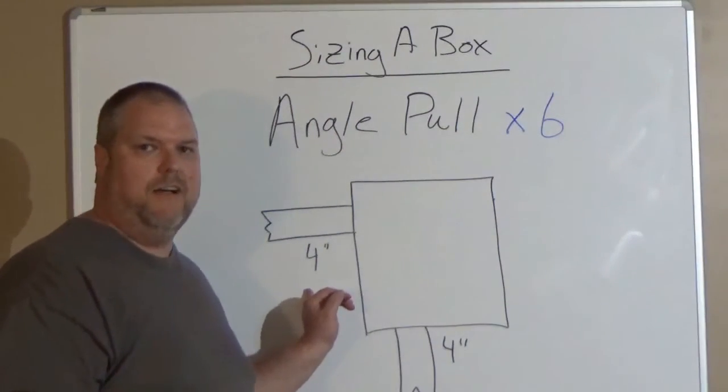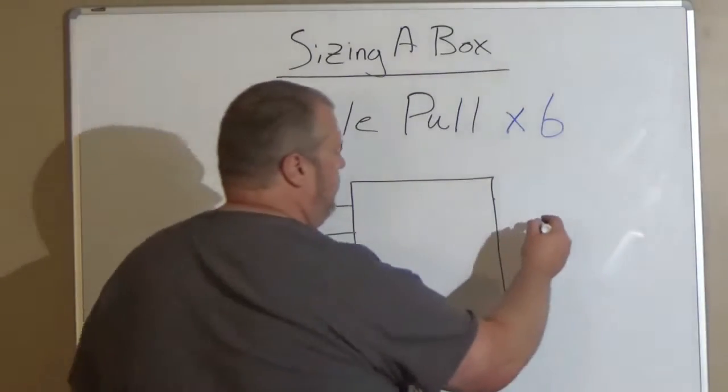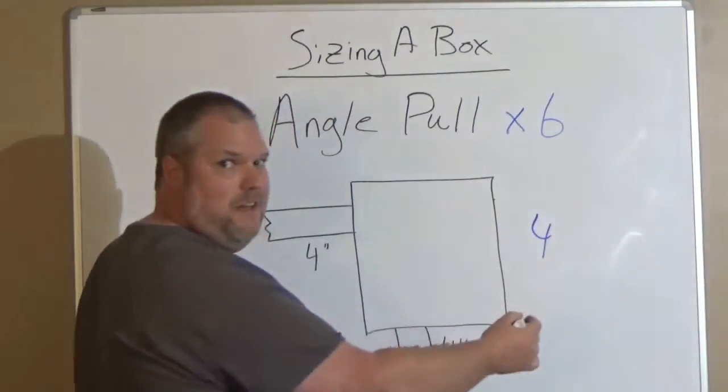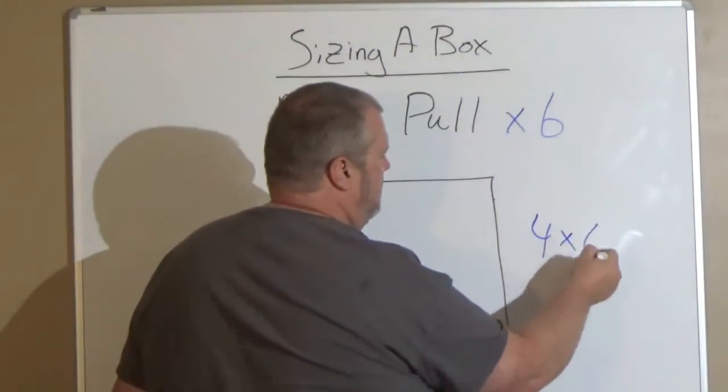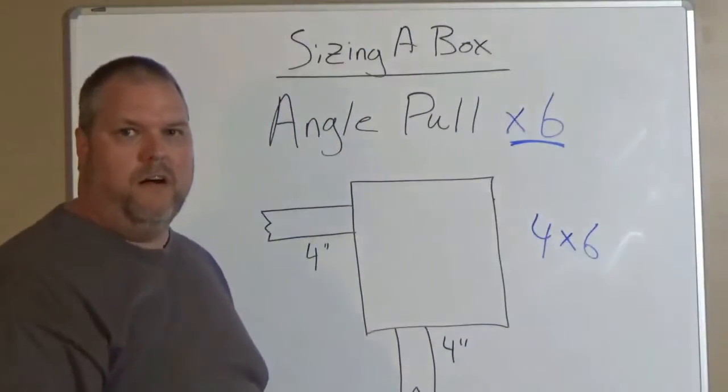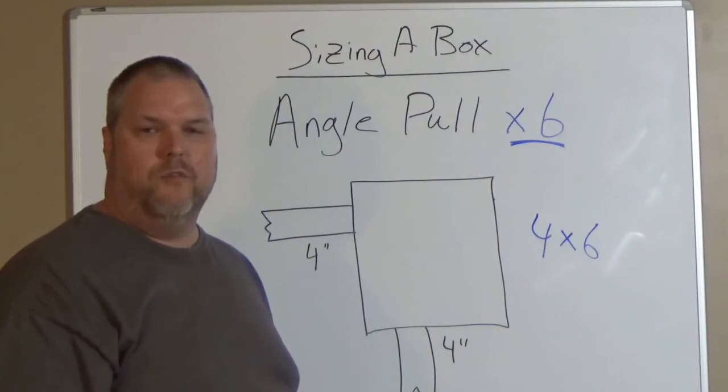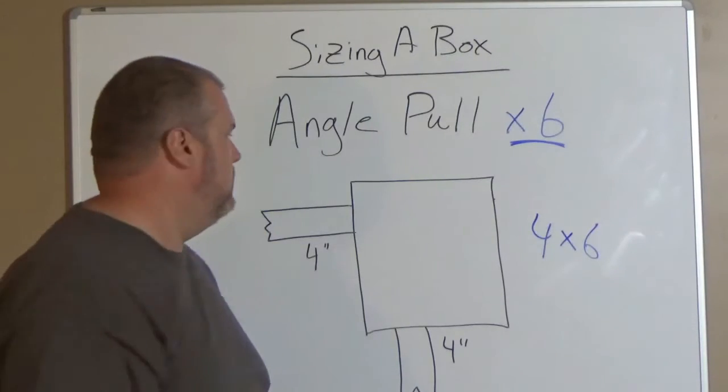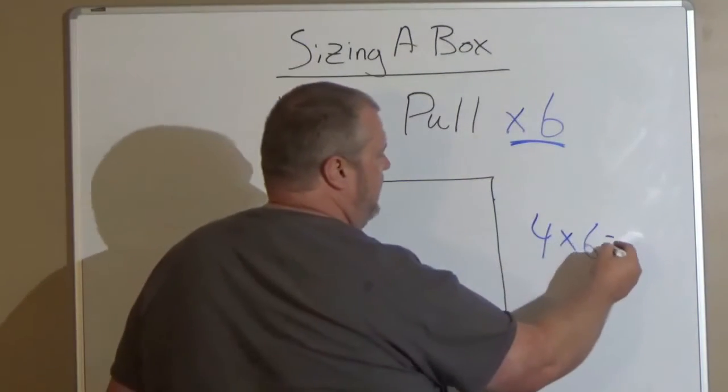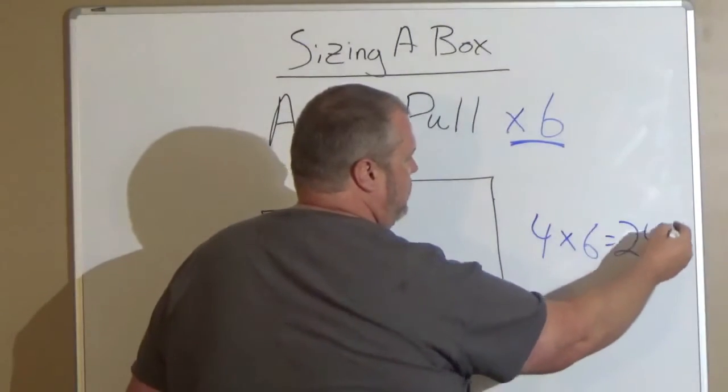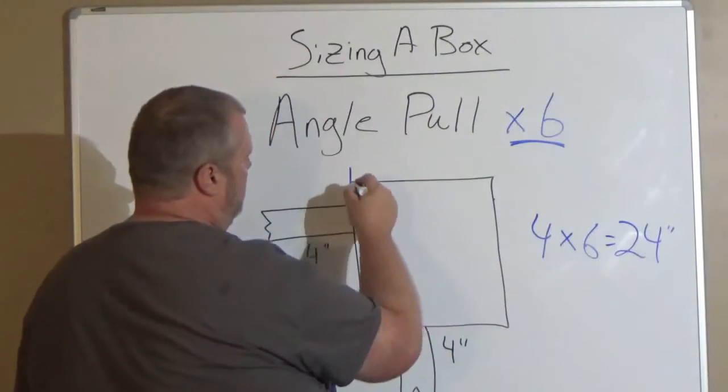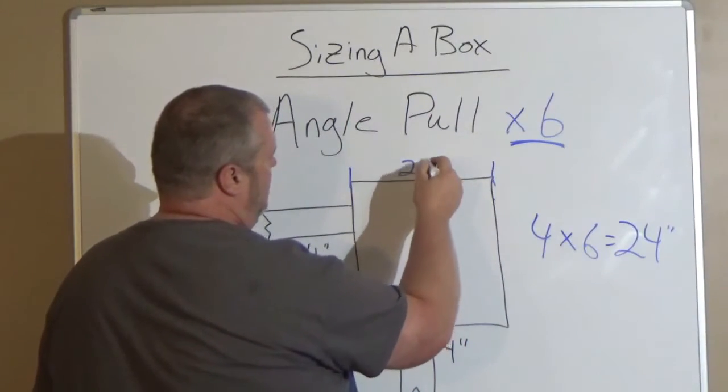My 4-inch conduit has to be sized, so I have to do 4, because that's the size of my conduit, times 6, because that's my multiplier according to Article 314.28A2. That's going to give me 24 inches. So this junction box has to be 24 inches.